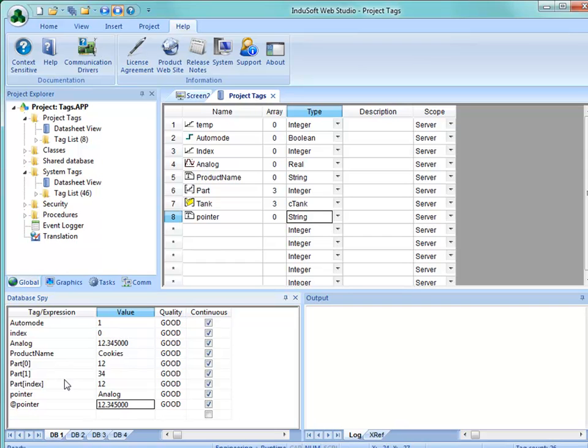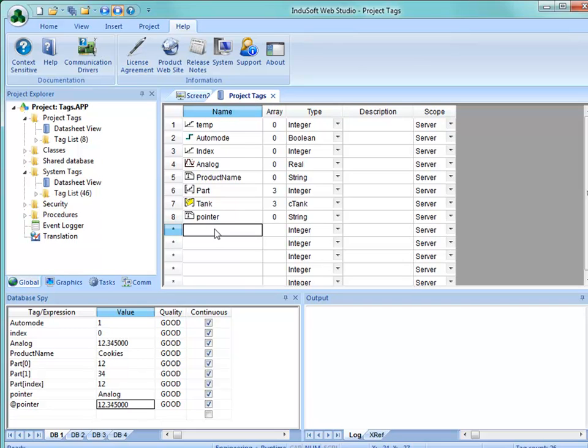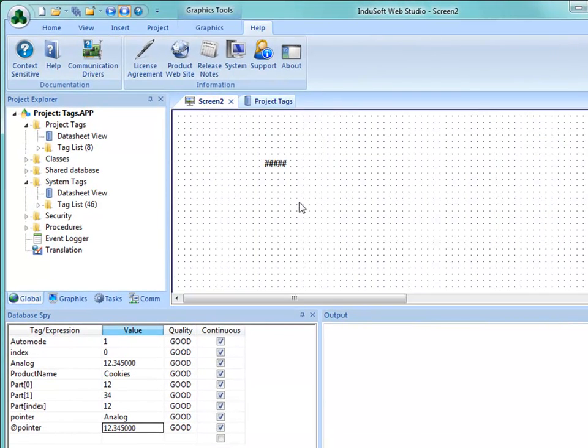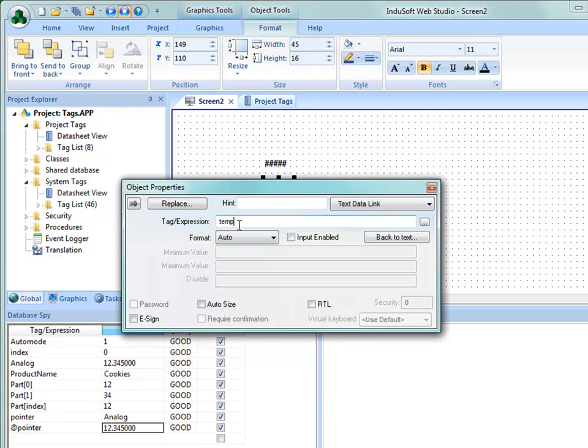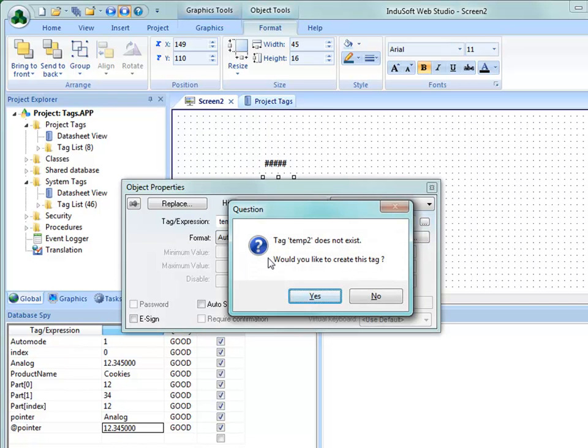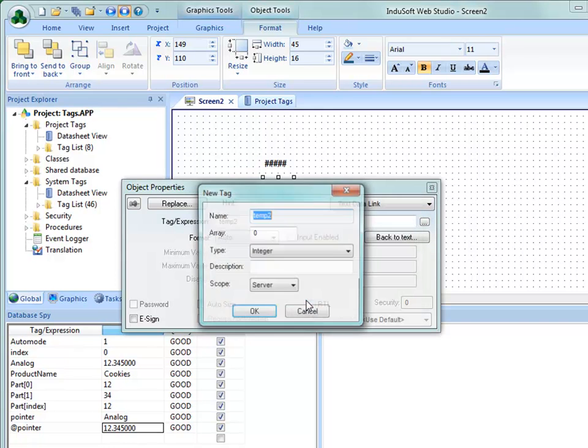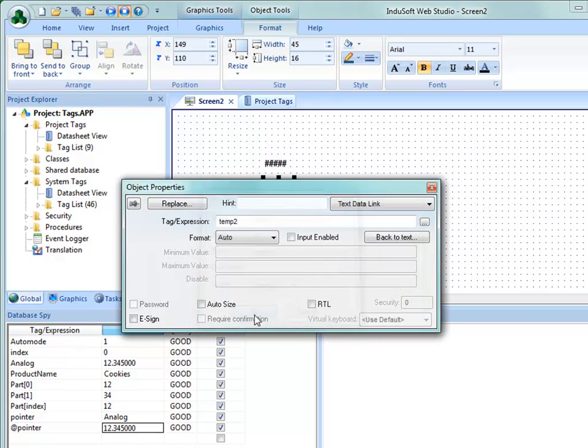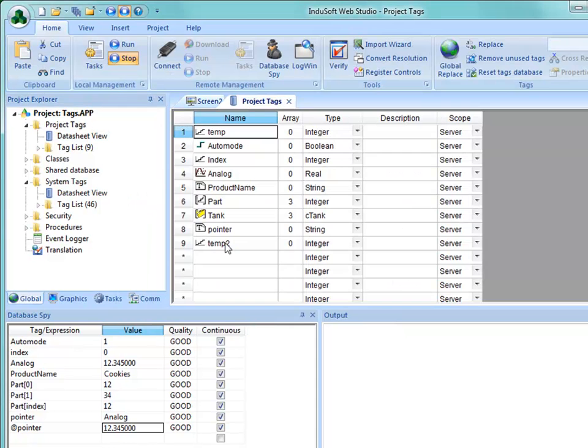The project tags list is sorted in the order the tags were created — whether you create them in the datasheet or on the fly within a screen. For example, I can copy an object that has a tag called 'temp', create a new tag called 'temp2' — it recognizes this because tags must start with a letter and it fits all requirements. When I hit Enter, it asks if I want to create this tag; I say yes and then OK. Going back to the datasheet view, you can see it's created at the bottom of the list.